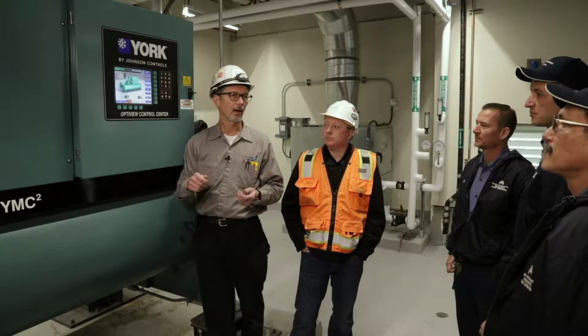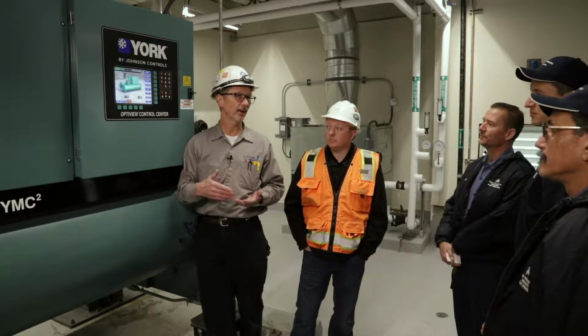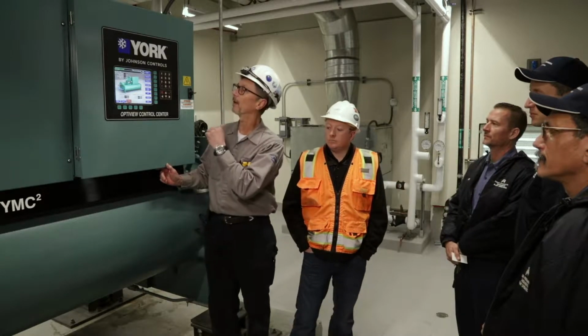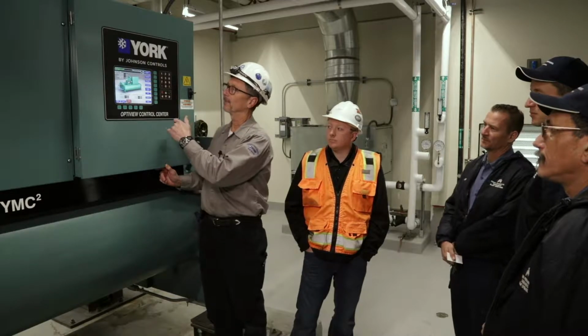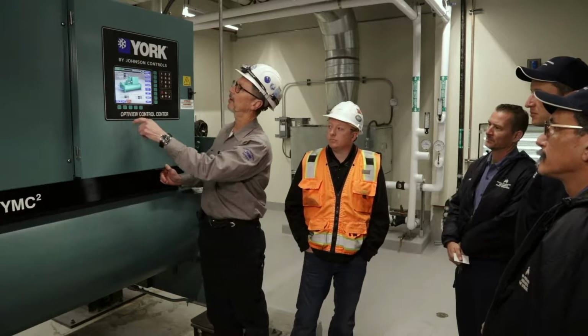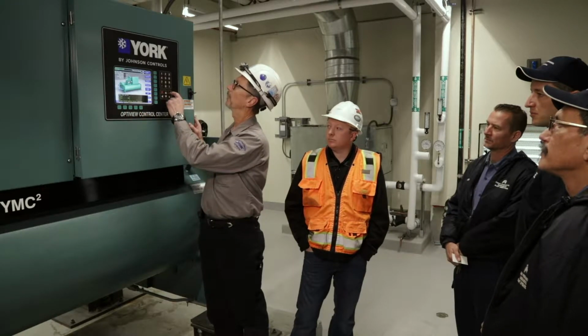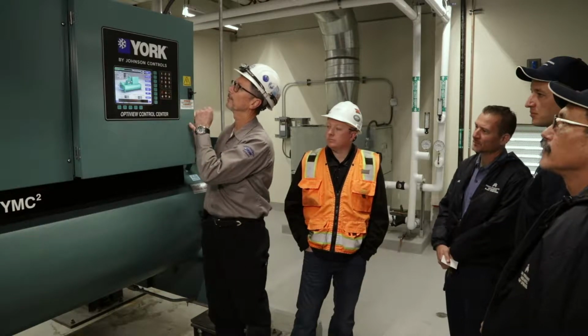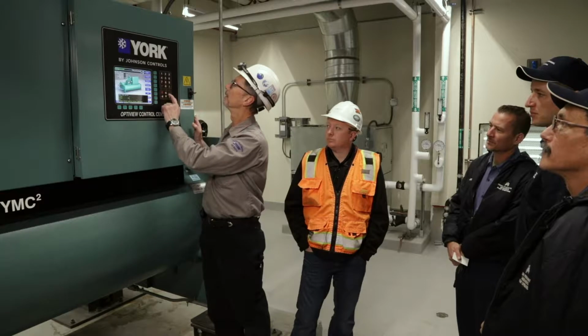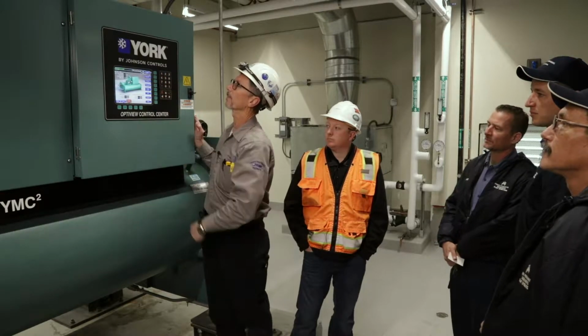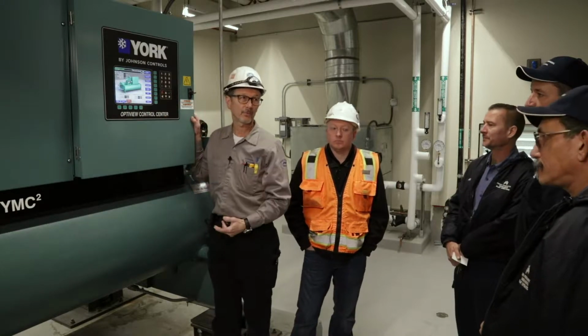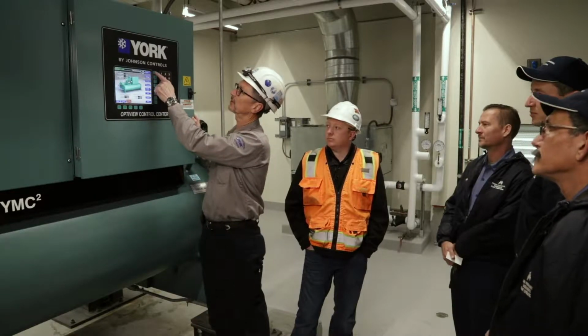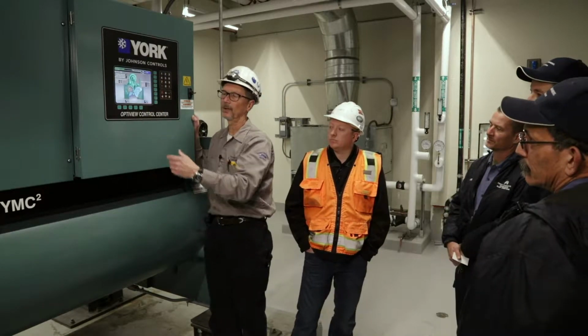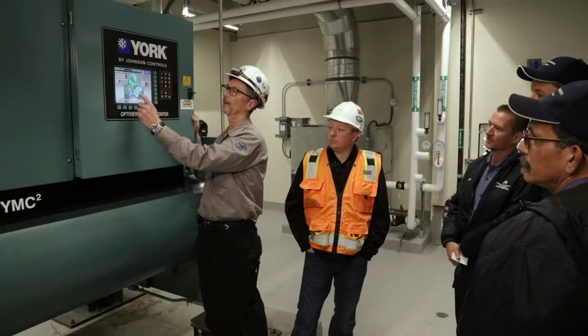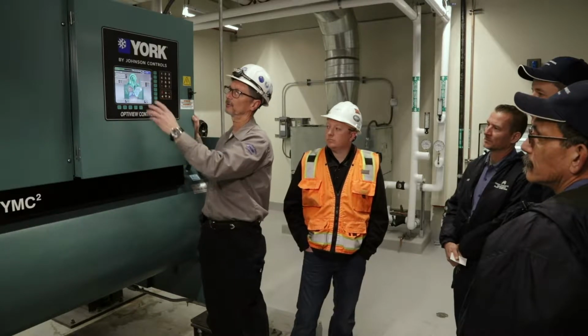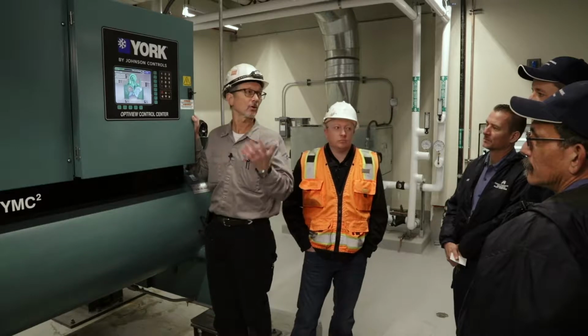And I'll go through and highlight some pages for you to identify some things. So first, on the home screen, when you log into this chiller, you're going to log in under service mode. So someone's already logged in, I'll log out. So we'll log in. We'll push enter. So we're logged in, so now we can see virtually everything in the OptiView panel. So first is the system screen. When the chiller's running, this is a good overall view of what's going on inside the chiller. Both evaporator, condenser, and the compressor and the load. So you can push that screen just to see an overall look of what's happening.